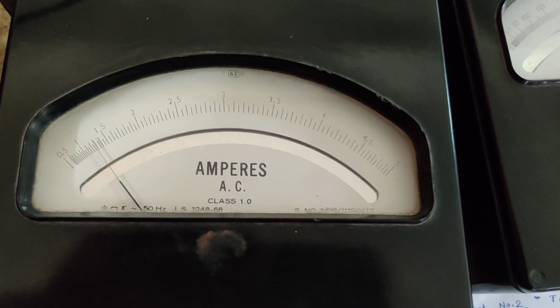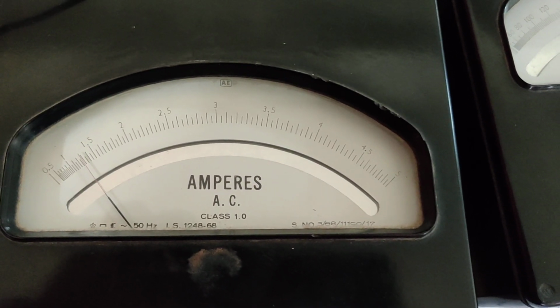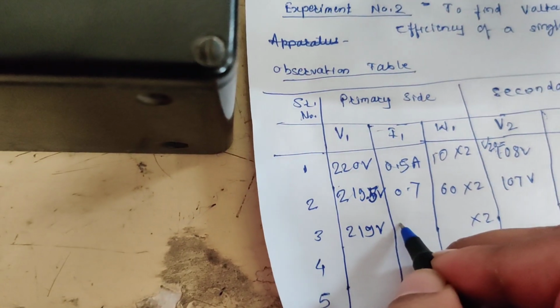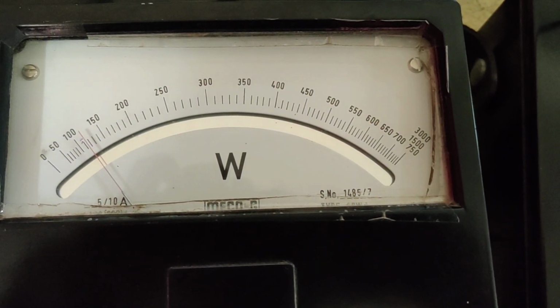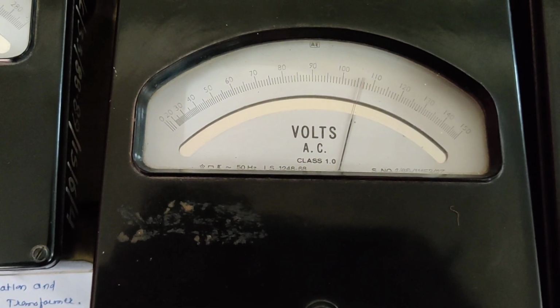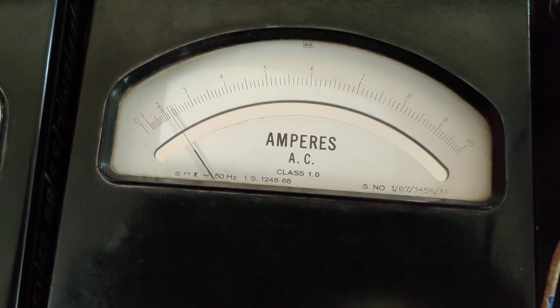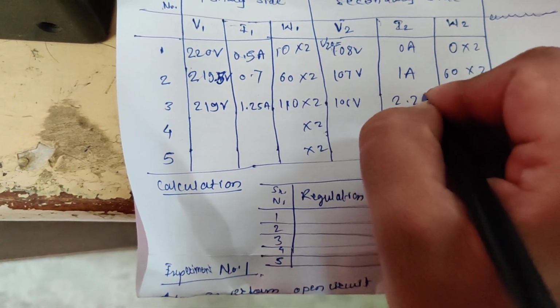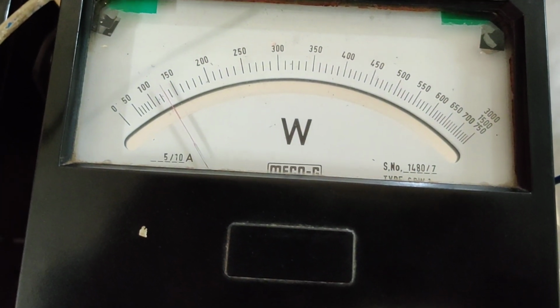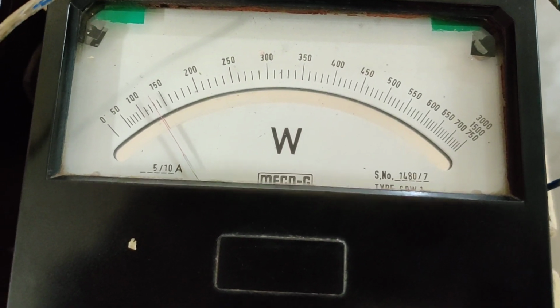So now this is the primary side voltage, this is primary side current, 1.25. So here it is 1.25 ampere. After that the wattage is approximate 110 watt. Then the secondary side voltage is 106 volts. Then the secondary side current is 2.2 ampere, and secondary side wattage will be 130 watt.